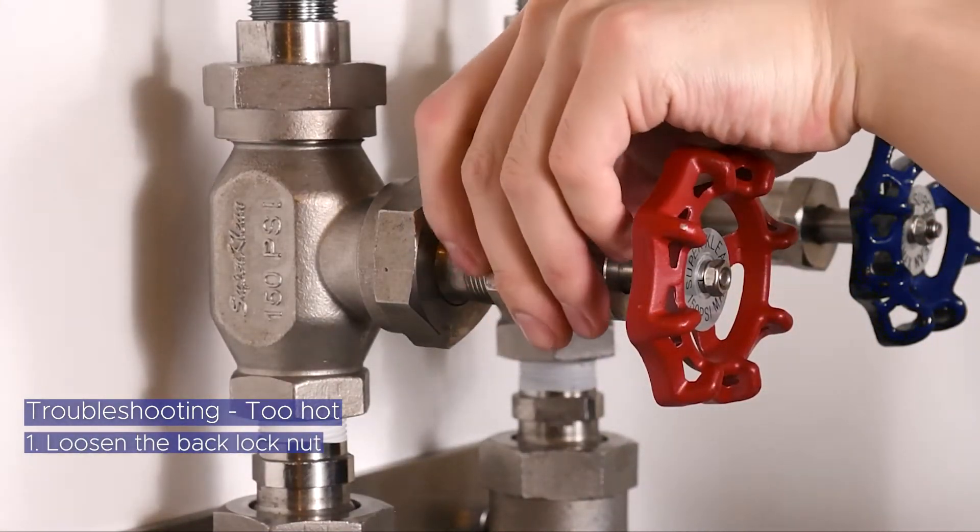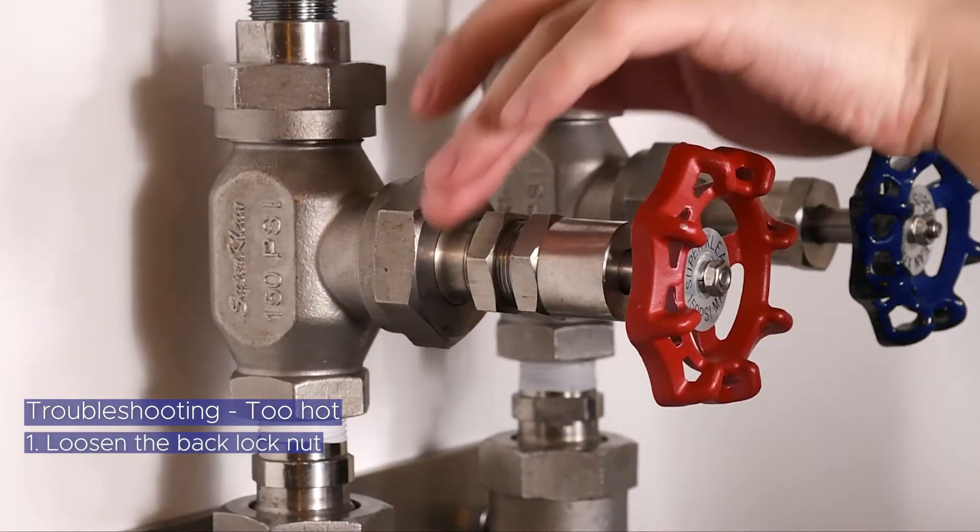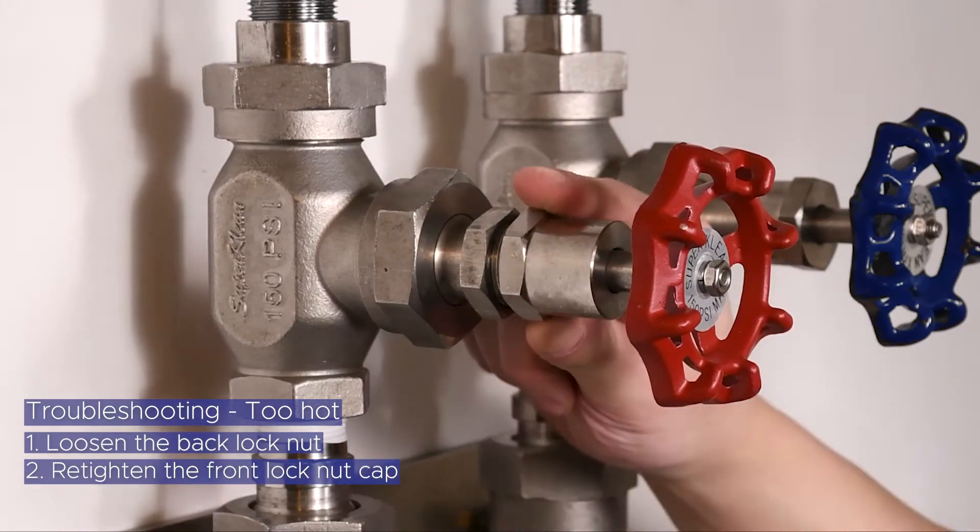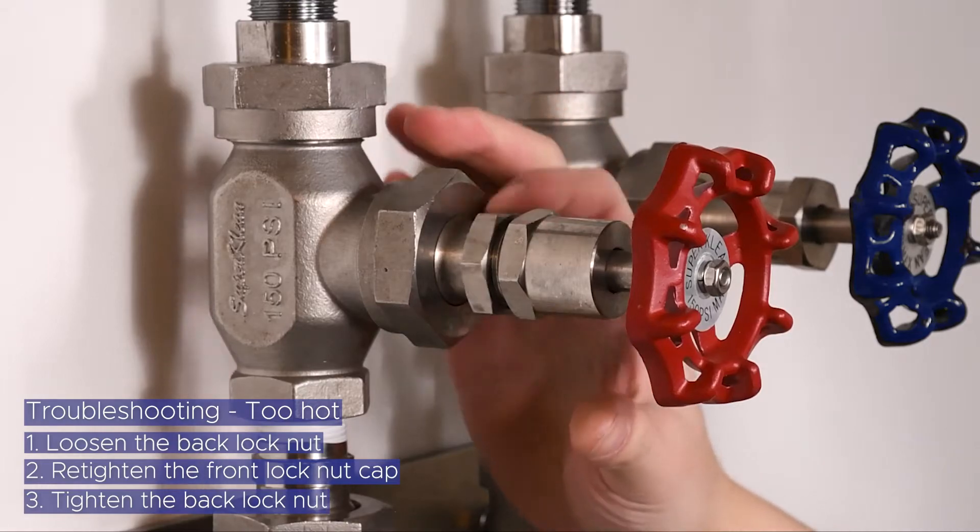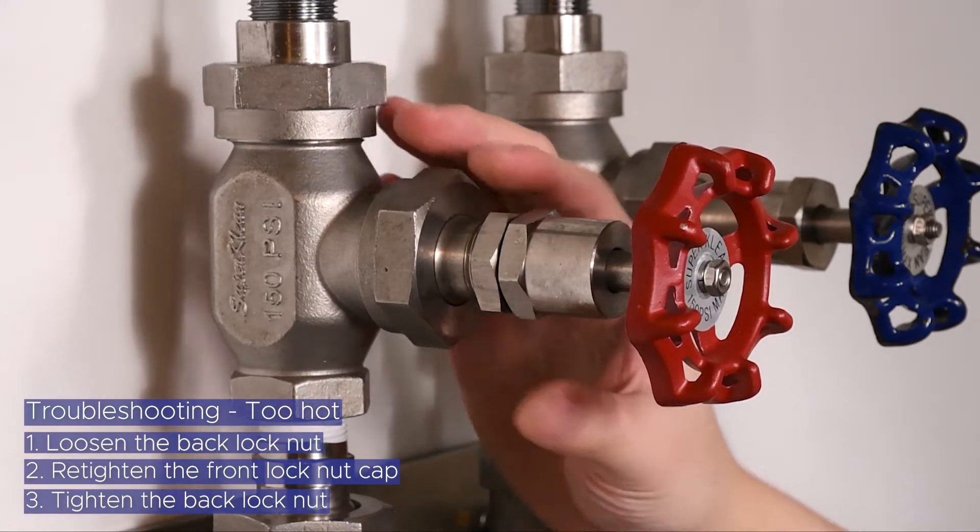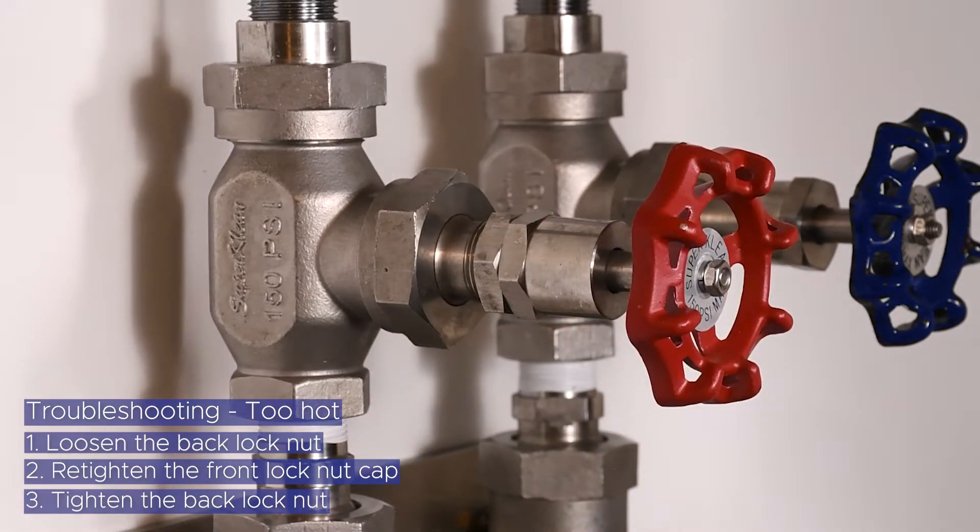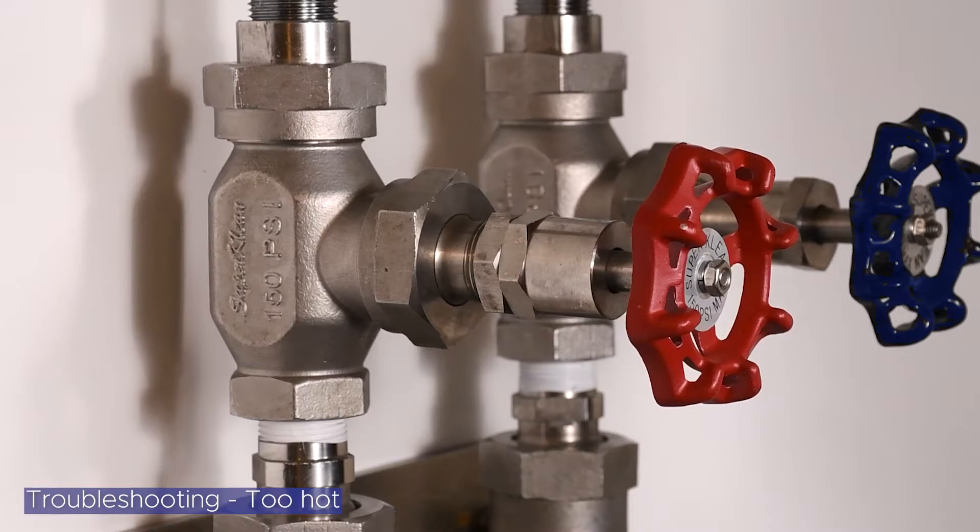loosen the back lock nut by turning clockwise, then retighten the front lock nut cap by turning clockwise until hand tight. Turn the back lock nut counterclockwise until hand tight to secure the lock nut cap. You will now achieve the same water temperature output with every operation. No further temperature adjustments are needed with everyday operation unless your desired water temperature output changes. Simply open the globe valves to begin operation and follow the regular shutdown procedure.